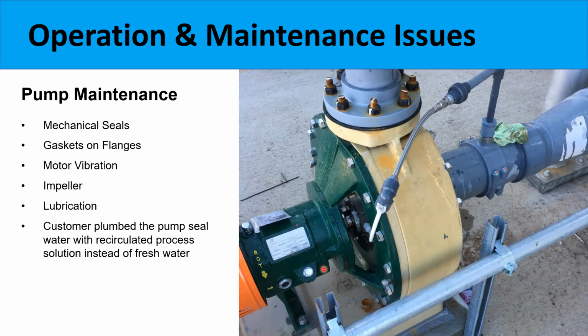In this case, we have a horizontal centrifugal pump that was provided, and one issue that we see here is that this pump seal requires water for lubrication, or really to keep the seal cool. In this application, the plumbing company accidentally plumbed the process water into this pump seal, mechanical seal location, and that process water contained some corrosive chemicals. So it should have had fresh water piped to it, which would have really helped that seal out. But in this case, we had a pump issue that caused a premature failure of the mechanical seal.